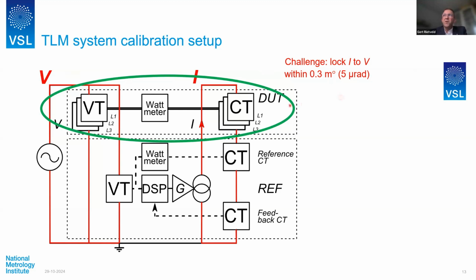So to generate a current with an adjustable phase angle, with a very stable, low noise phase angle, and also with an accurate value so that you exactly know what the losses are that you are applying. To this end, we measure the voltage, and we do digital signal processing in order to get a driving signal for the current circuit here. And then, of course, there's a feedback system. We measure the actual applied current and compare it to what we would like to have. And if it's not exactly the phase angle we would like to have, we adjust our driving signal in order to get it right.